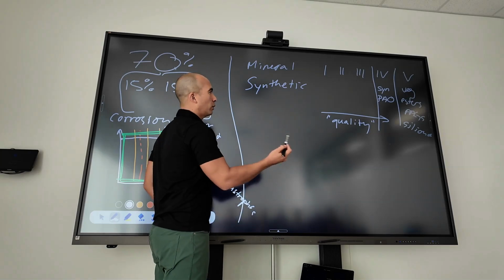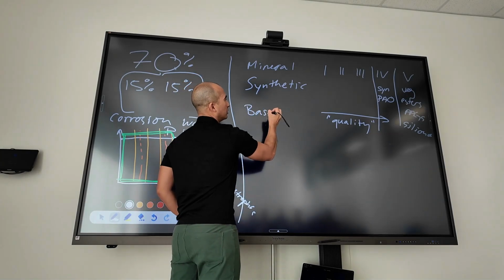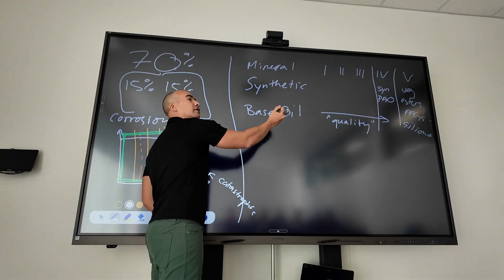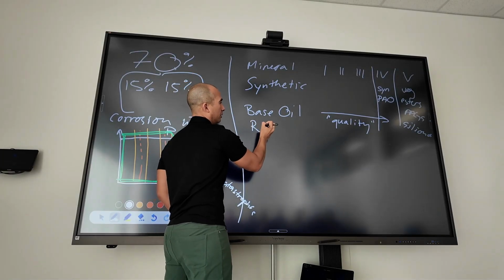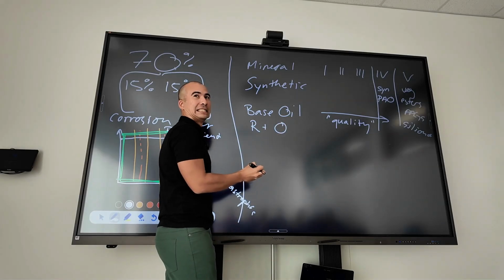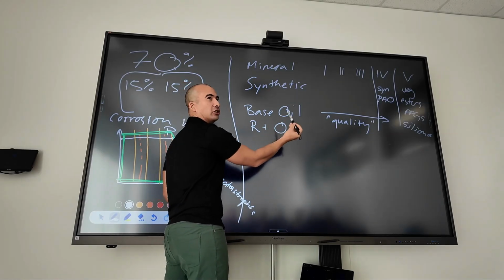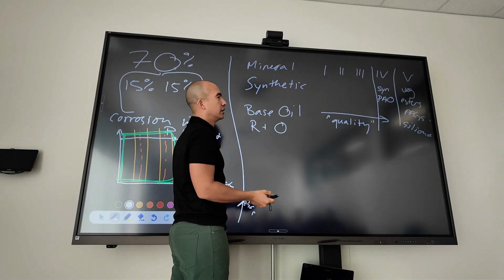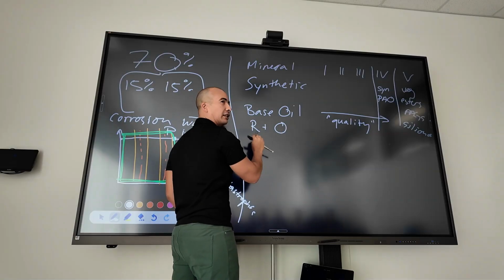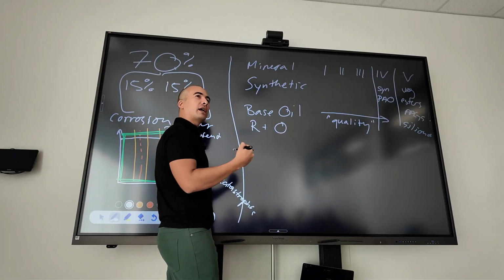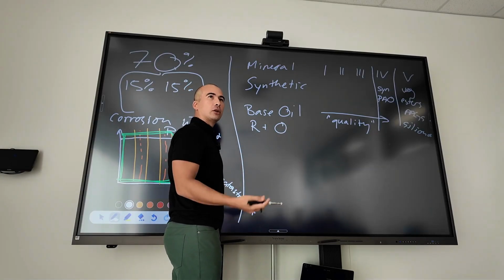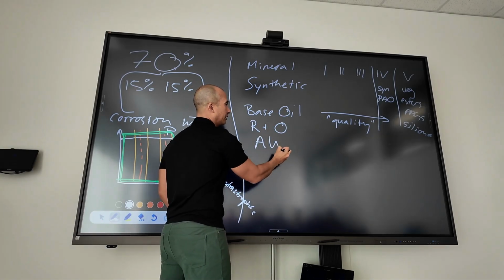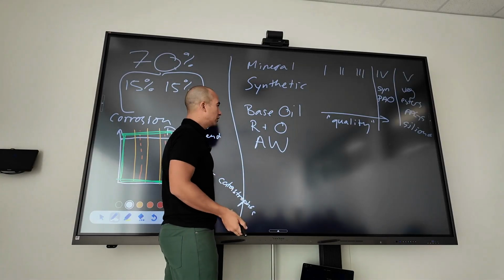If you remember, the way we construct an oil, first of all, we start with our base oil. The next thing we do is protect the base oil. So we add, does anyone remember what that is? That's rust and oxidation inhibitors. The rust and oxidation inhibitors are there to protect the base oil primarily. The next thing might be, if I have a little more load in the application, I've got to protect the surfaces against wear. So I'm going to use anti-wear. Pretty simple, everything's very descriptive.